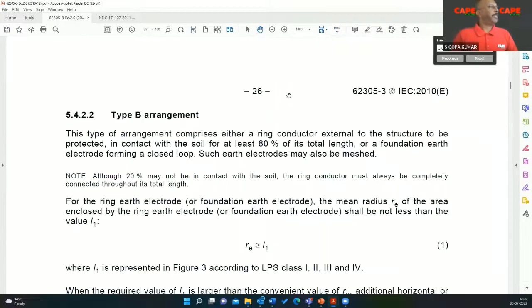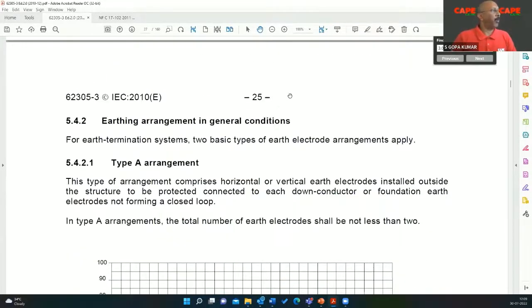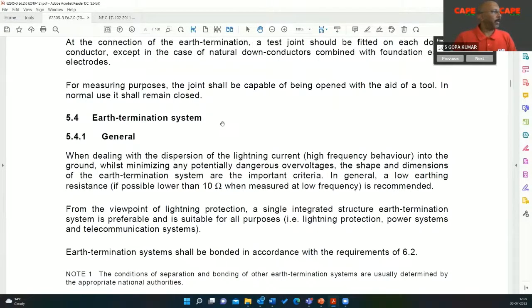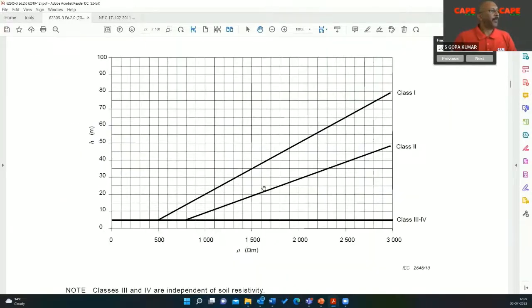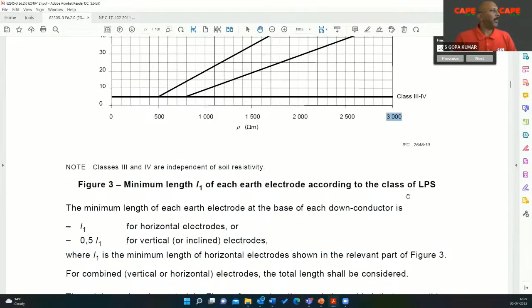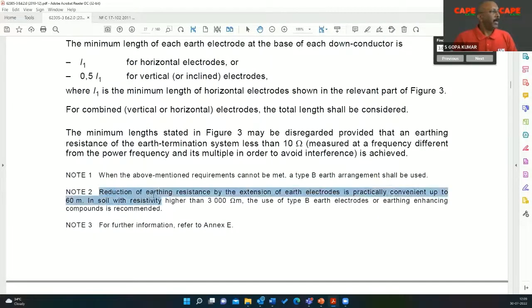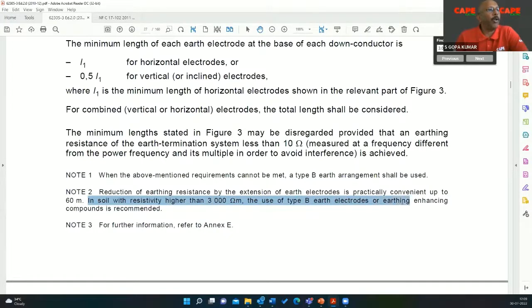So here is the table. You can find this particular picture in the standard. Here you can see the section is 5.4.2 or 5.4, earth termination, how to make earth termination. Now you look at the picture, up to 3000 ohm meter is shown. Now you read the note here. Reduction of earthing resistance by extension of earth electrode: several techniques are there. One of the techniques is extending the earthing conductor in the soil, practically convenient up to 60 meter. In soil with resistivity higher than 3000 ohm meter, see, the wording is very clear, the use of type B earth electrode or earth enhancing compound is recommended. So for more than 3000 ohm meter, two techniques are there: type B earth electrode or earth enhancing compound is recommended.